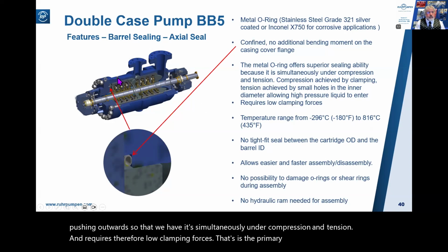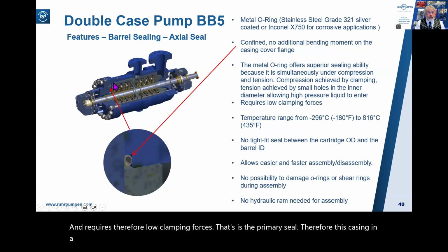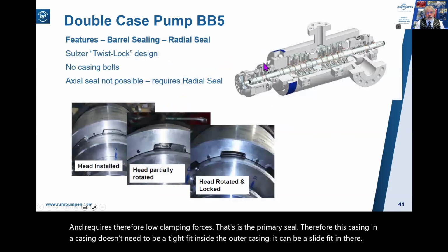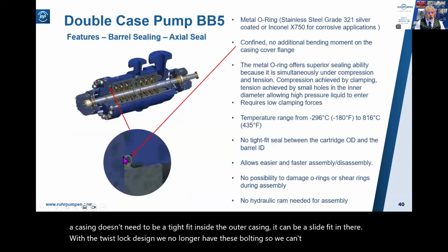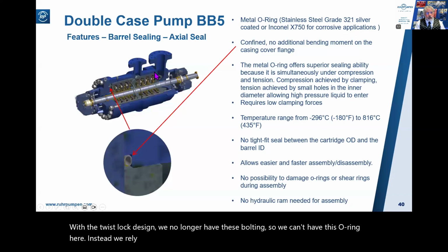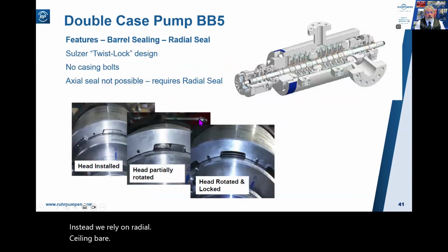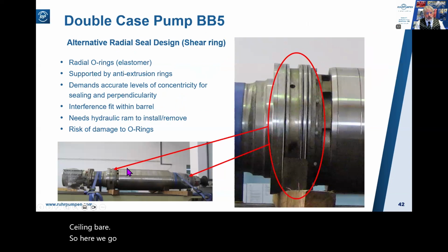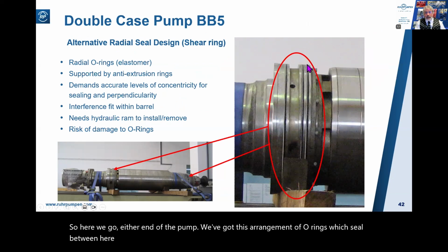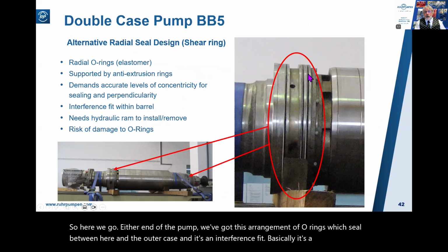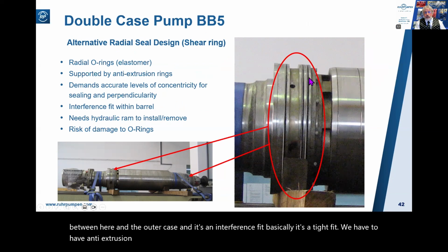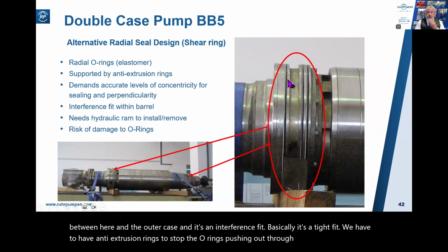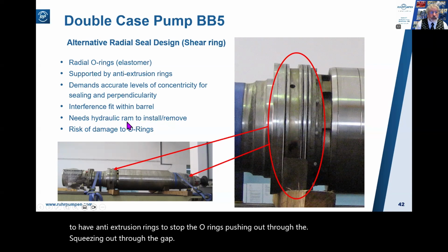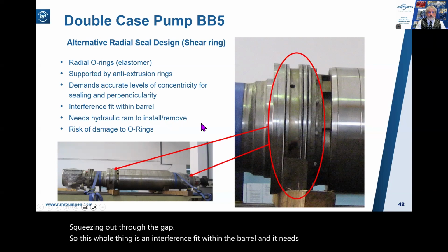That is the primary seal. Therefore, this inner casing doesn't need to be a tight fit inside the outer casing. It can be a slide fit in there. With the twist lock design, we no longer have this bolting, so we can't have this O-ring here. Instead, we rely on radial sealing there. So here we go. Either end of the pump, we've got this arrangement of O-rings, which seal between here and the outer case. And it's an interference fit, basically. It's a tight fit. We have to have anti-extrusion rings to stop the O-rings squeezing out through the gap. So this whole thing is an interference fit within the barrel, and it needs a hydraulic ram to install or remove.